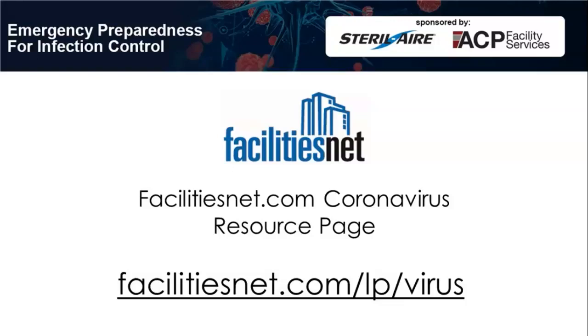If a portable UVGI is used, what forms of protection should the user wear? Sure, yeah. So you have to be careful. You have to cover your eyes. Even just the glasses that you wear are enough to protect your eyes. 3 millimeters of plexiglass will protect you from UVC. UVC is really not that hard to protect yourself from.